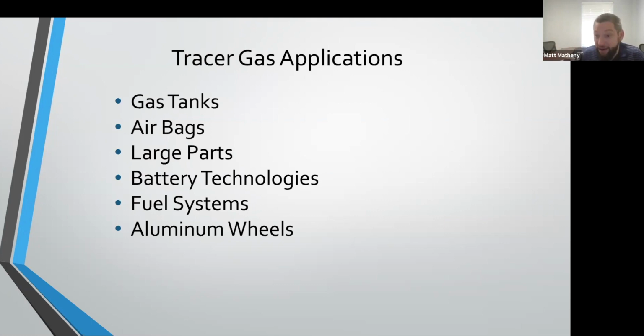Are they going to always do that? We know human error is a thing, even with the most attentive person. And that takes a long time—with sniffing, it's generally recommended that you spend 2 seconds per joint. So if you have a huge heat exchanger with 400 braze joints, that's 800 seconds of sniffing, not counting any other part of the process. So it might make more sense to use a chamber rather than sniffing.